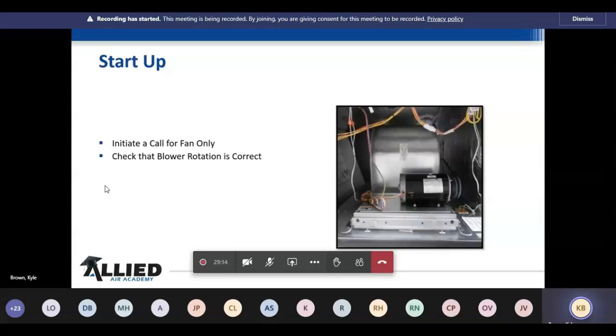Now, there's a couple of different ways of changing rotation. We all know to switch two wires. It's where you switch the two wires at. So the instructions will tell you to do it at the contactor or do it at the power coming in. If you do it at the contactor for the blower motor, that's all fine and good. But we need to be very careful of the wiring diagram and where the wires land on that contactor.